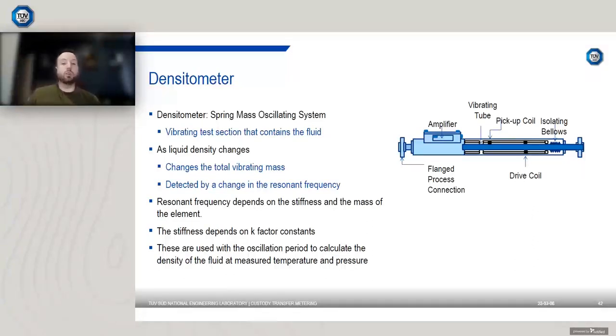The frequency depends not only on the mass, but on the stiffness of the measuring tube. The stiffness depends on constants that usually are provided by the manufacturer, or you can get them through calibration. Then you use that with the oscillation period, which is just the inverse of the frequency, to calculate the density of the fluid at a measured temperature and pressure. To put it simply, denser fluids will vibrate at a different frequency than less dense fluids. So by measuring the frequency, you can determine the density of your fluid.